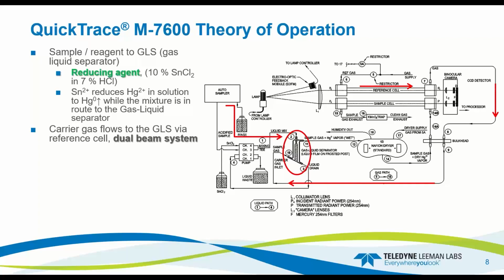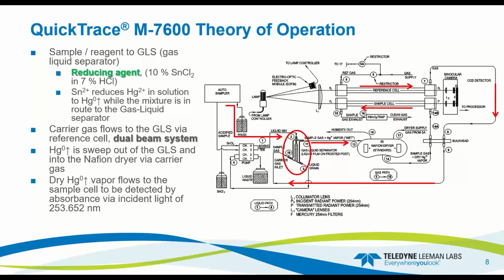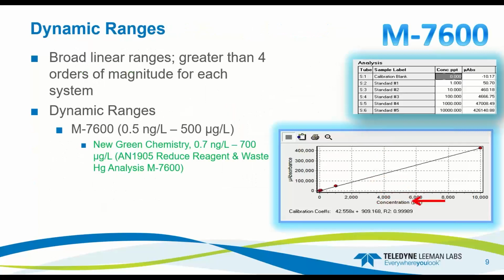The sample gas flows in through the reference cell, flows out of the reference cell, and makes its way over to the gas liquid separator over here in this dual beam system. From there, the reduced mercury or the elemental mercury is going to pass out of the gas liquid separator, go through the Nafion dryer, and end up in the sample cell where it's measured at 253.652.